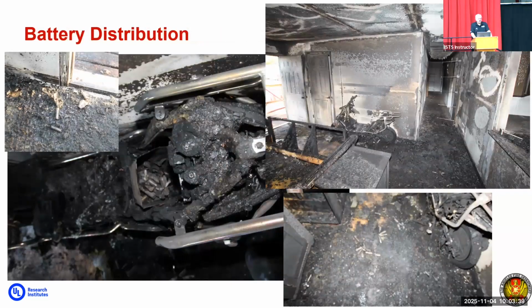Battery distribution, batteries were everywhere. So this is an issue for mop-up. Some of these ejected batteries might have gone into thermal runaway, some not. Some could be unstable, some damaged, but they have stranded energy. There's been at least one reported incident I'm aware of where a fire investigator picked up a loose battery cell off the floor and had it discharge in his hand. So again, gloves, full PPE when you're cleaning up from one of these fires.